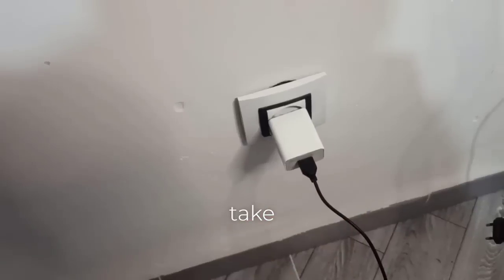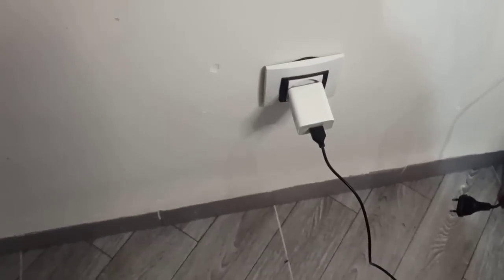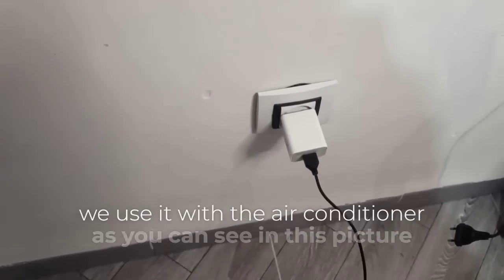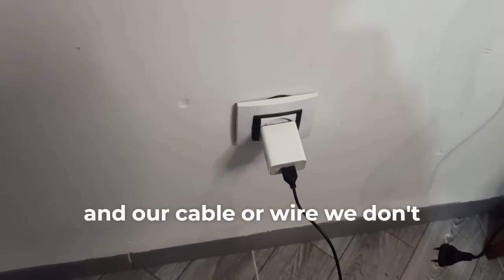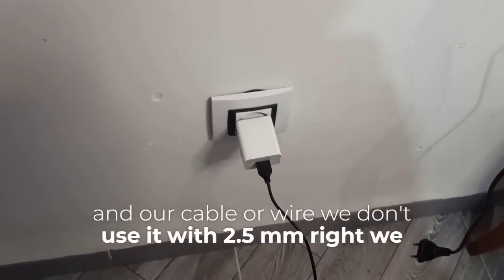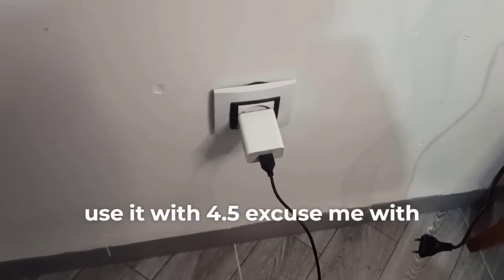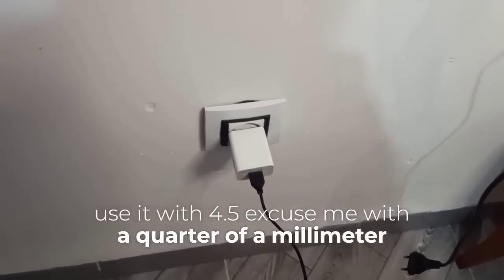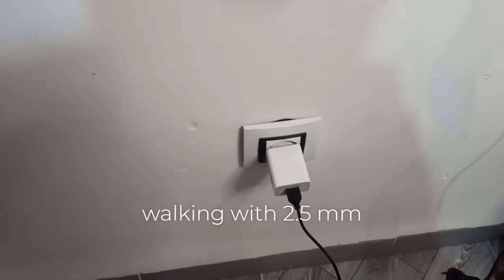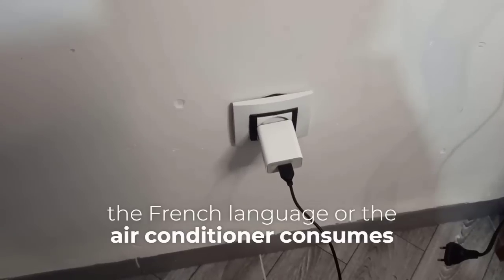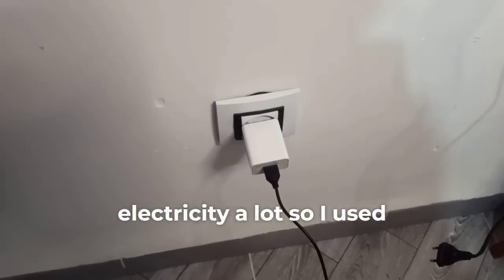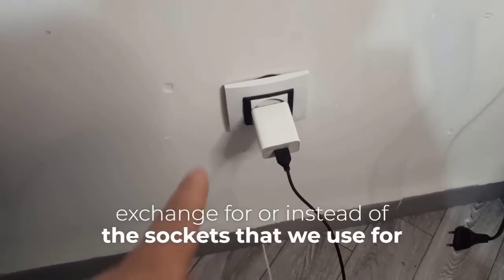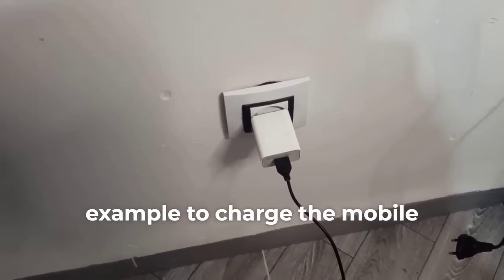Breaker number 3 we use with the air conditioner, as you can see in this picture, and for our cable or wire, we don't use 2.5 mm. We use 4 mm, because the air conditioner consumes a lot of electricity, so I use the 4 mm cable instead of the 2.5 mm used for the sockets that we use, for example, to charge mobile phones and also for the TV.